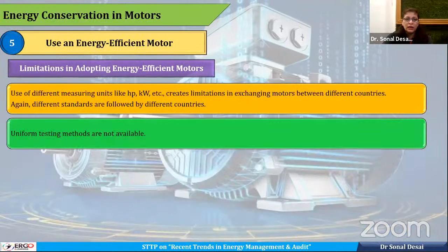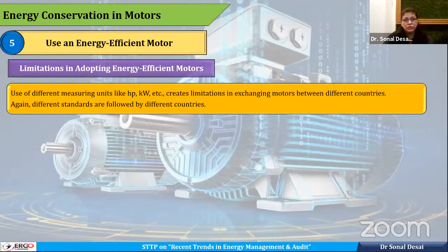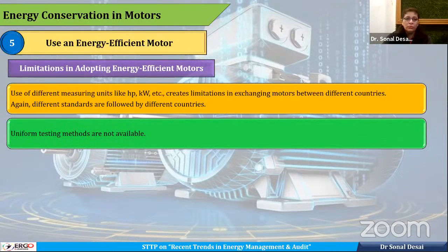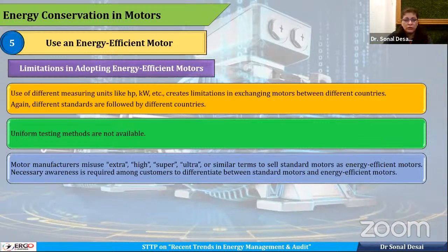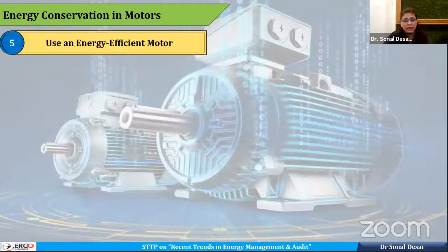Some more limitations: there are different measuring units, like some follow HP, others follow kilowatt. So that is also confusing among the countries and within. Uniform testing methods are also not available. That is also an issue. And motor manufacturers also misuse jargon like extra efficient, high efficient, super, ultra. Whether they are selling standard motors or energy efficient motors, there are no standards, they can use any word. So these words are misleading to laymen. Those who are non-technical persons always believe that when you put a word like high, it's good. It's like a rating. When you put 5-star, it is better. Something like that, the same thing happens in motors too.